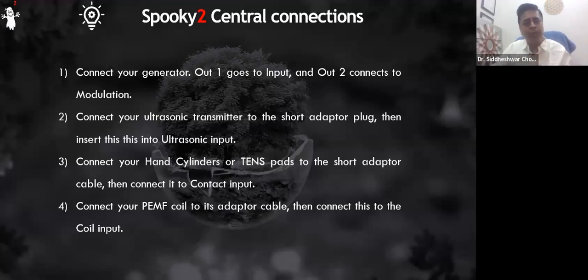Once you make these connections, whenever you tighten the BNC cable, turn it clockwise to lock it. Some people miss that, resulting in improper connections. If you don't lock it and the wire gets pulled, the connection could be lost, so make sure you lock the cables. To check, always pull it out and see if the connection is proper.